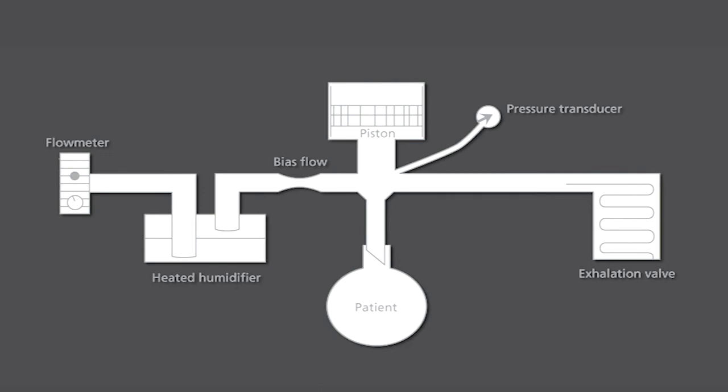This diagram represents a simple schematic of the ventilator circuit. The bias flow enters the system and passes through the humidifier, where it is heated and humidified prior to delivery to the patient.